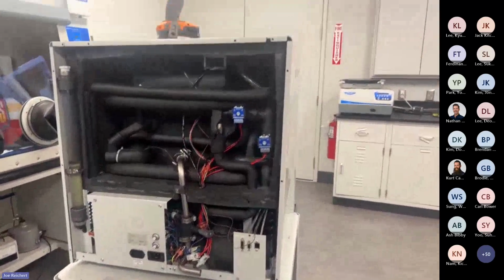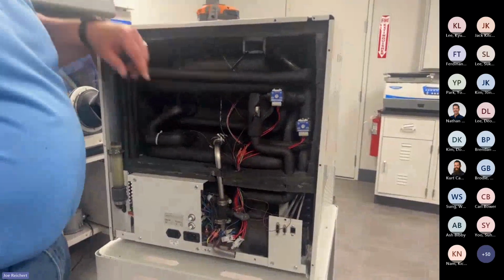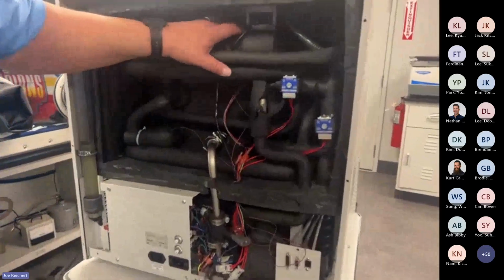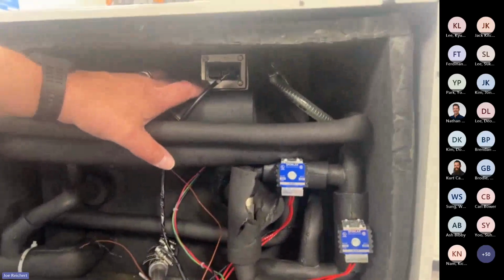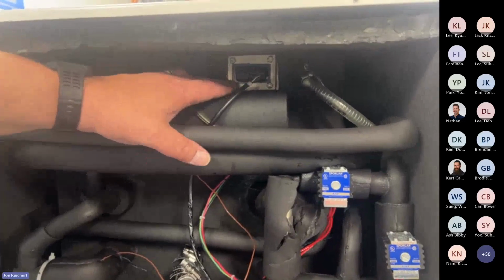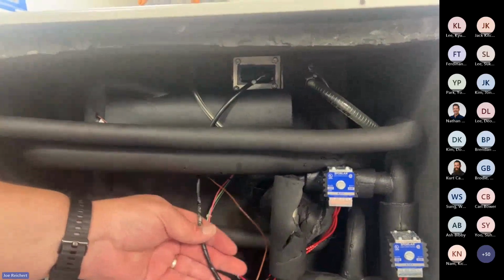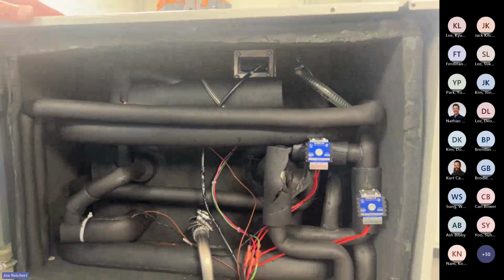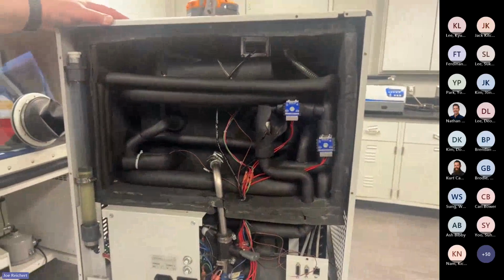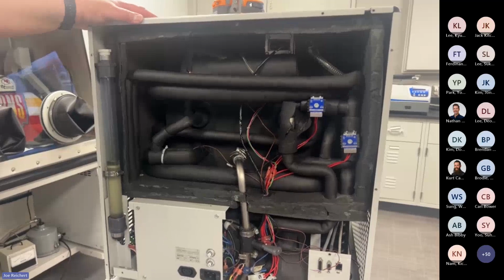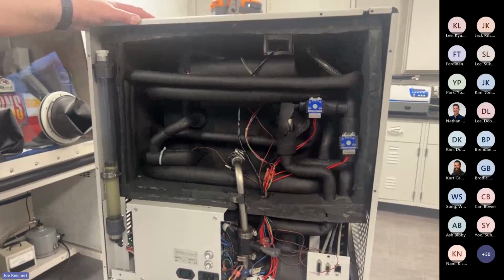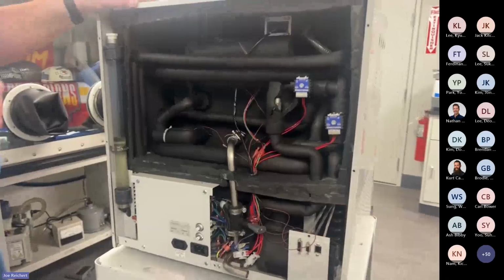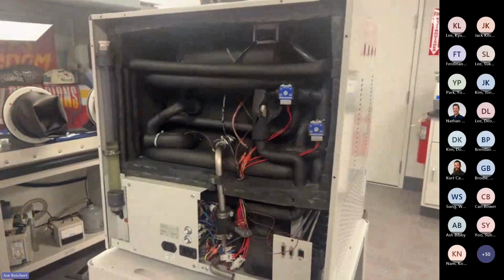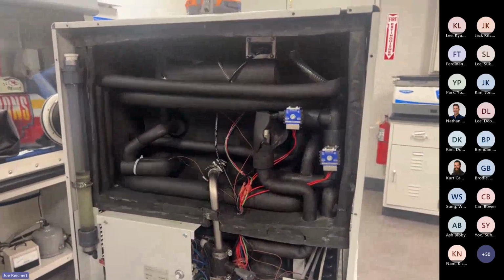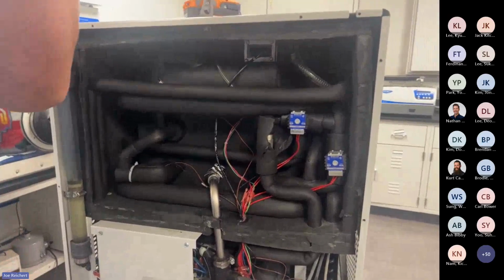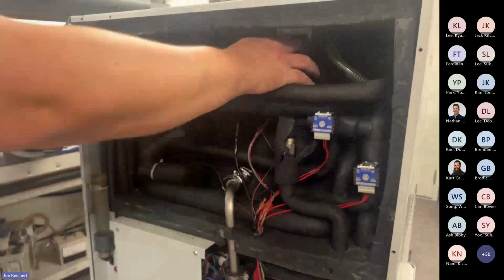Next thing is just taking the whole wrapper off. Here's your pass through again on the back, as we saw on the inside of the chamber. The pass through goes all the way through, and this is your temperature wires coming through here. So if you ever have an issue with a temperature sensor showing dashes, it could be unplugged from the front, where I was showing how the customers can sometimes pull that out of there. But then you also have other connectors, like on the pass-through, where the wires can get pulled out of their connector there as well.